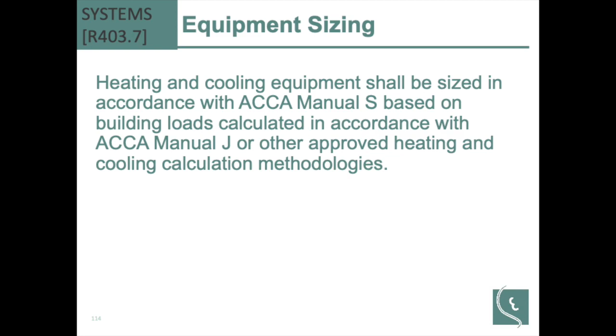Acca does have a manual J express sheet you can use at no cost. But equipment sizing is very important, particularly on the air conditioning side, because if I oversize a heater, it's not a big deal, but if I oversize air conditioning, I lose dehumidification, and that's a problem. Not that we want to oversize equipment anyway.